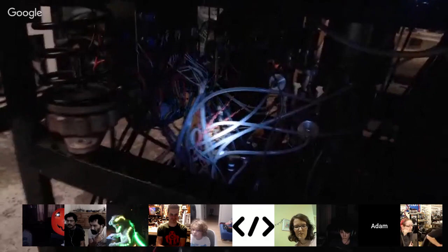It started with the diffusion pump, the wire on it had been damaged, like a rat got to it, and when you have a couple hundred volts in there you don't want that shorting out against anything. Once I got the wire replaced, I tried to get my water chiller working, because this thing produces a lot of heat, so you actually have to use water chilling to get it to work.